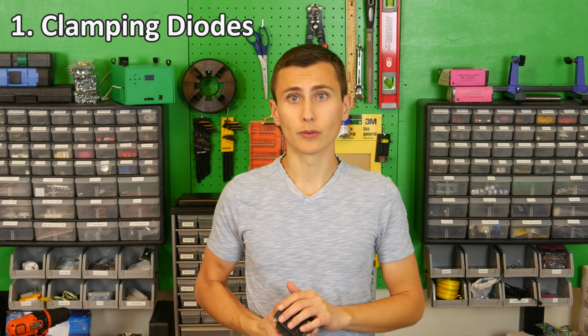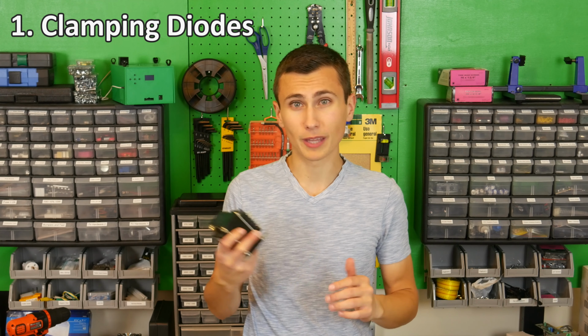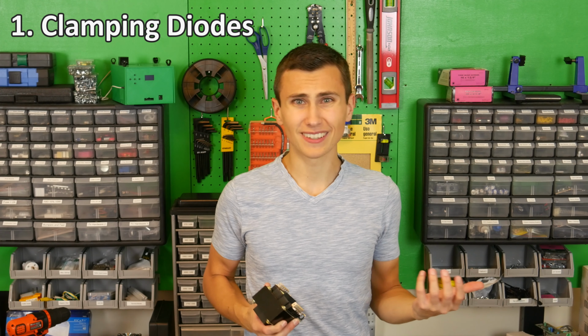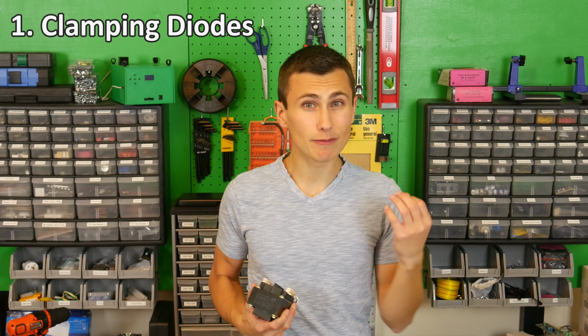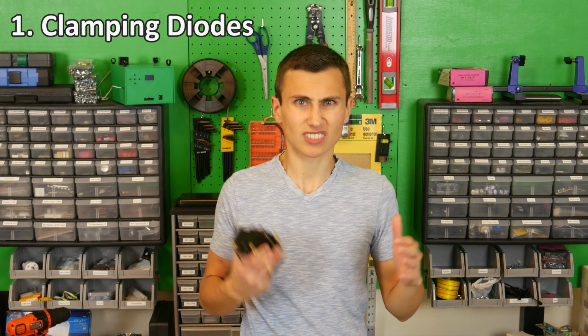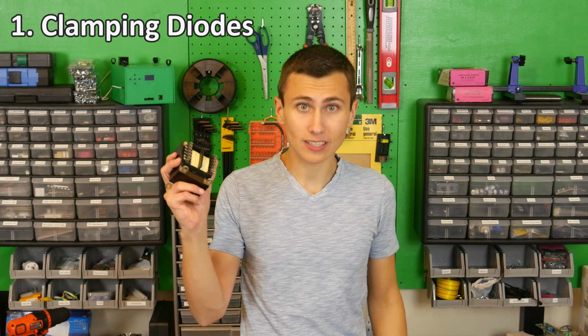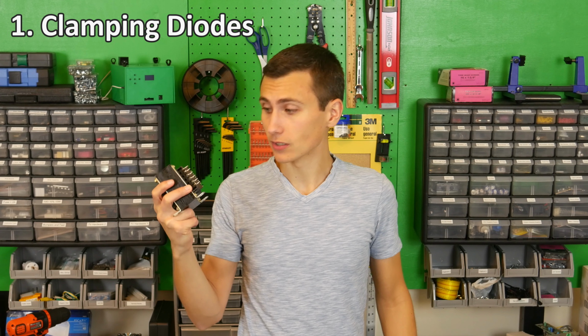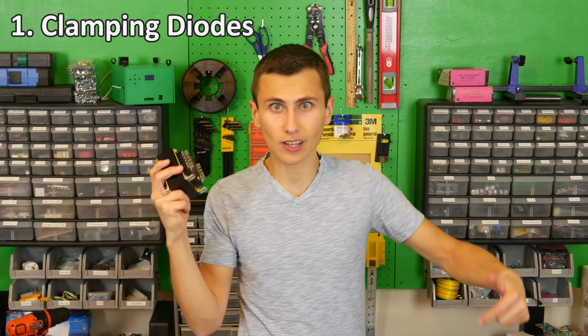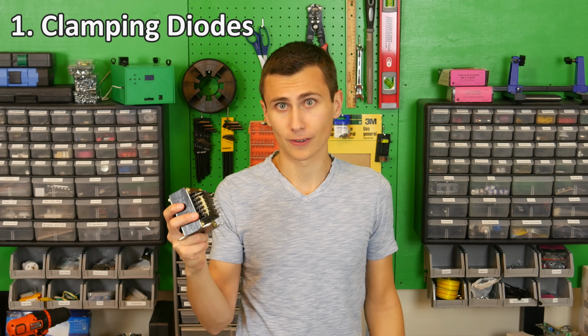A clamping diode will cause a little bit of current to leak from the output to ground, but it would completely destroy any voltage spikes due to transient inductive weirdness and protect the transformer winding so it doesn't weld itself to itself and short out the inverter.